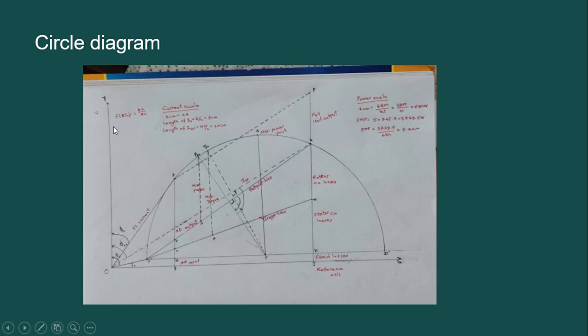Now let us construct the circle diagram. First, draw a positive Y-axis and positive X-axis. Along the positive X-axis it represents the reference axis, and along the positive Y-axis it represents voltage. Now measure phi naught as 78.93 degrees. From the origin, extend this line till O dash. The angle should be 78.93 degrees and the length from origin to O dash should be 3 centimeter, because this length represents no-load current, which is 6 ampere.